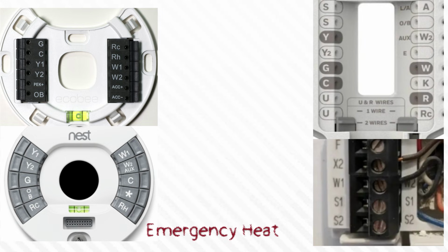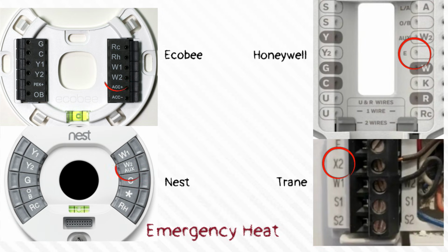Now, emergency heat can vary a little bit. On a Honeywell, you might actually see an E terminal. On a Trane thermostat, however, your emergency heat would be X2. On other smart thermostats like a Nest or an Ecobee, the auxiliary or W2 is actually the emergency heat. It's just in the programming and the logic of the thermostat itself. So if you set this up as a heat pump with emergency heat, the thermostat will energize emergency heat under certain circumstances through that auxiliary or W2 terminal.